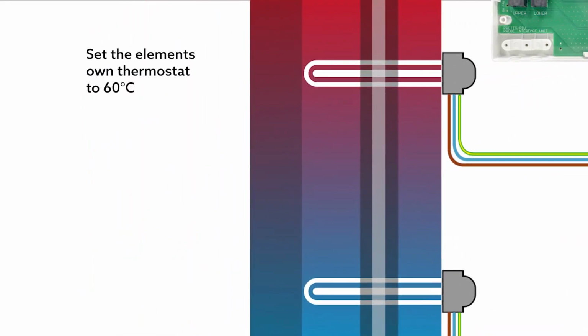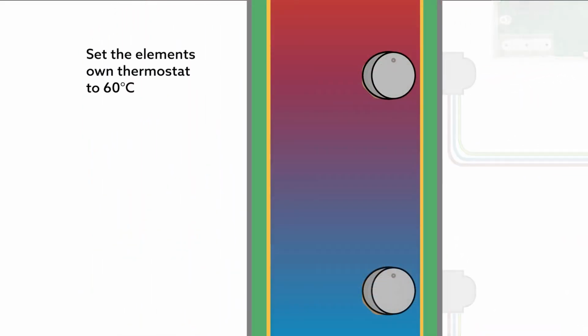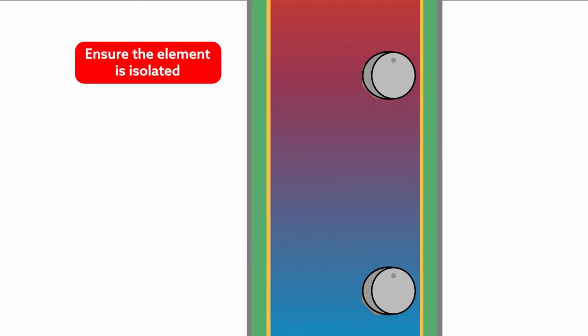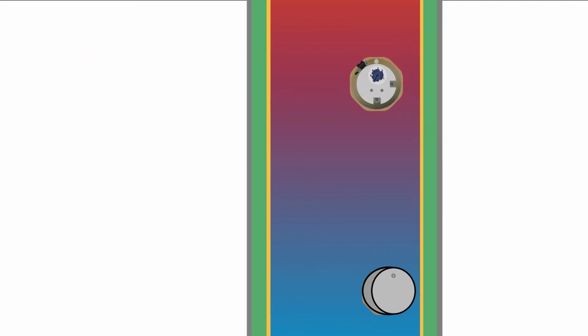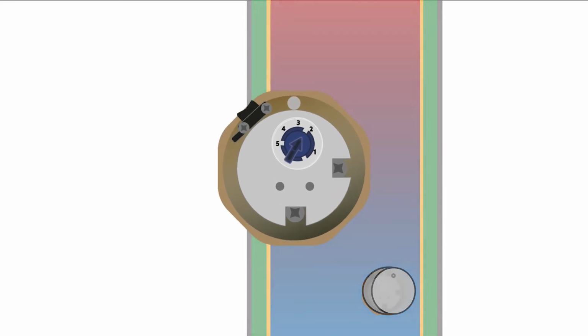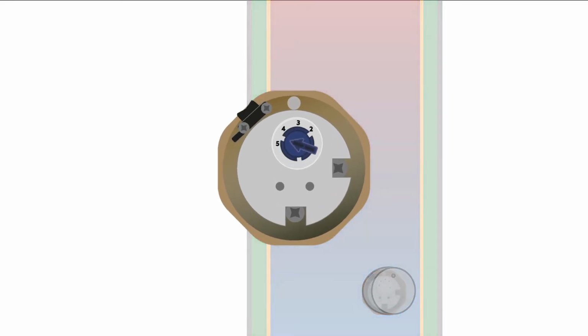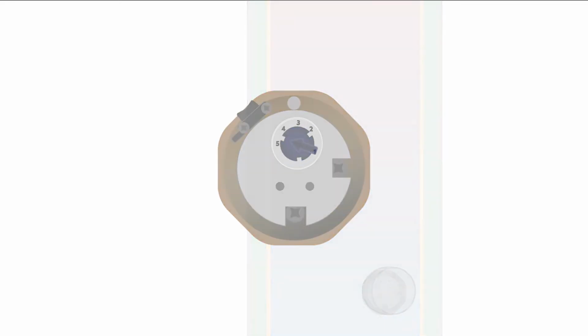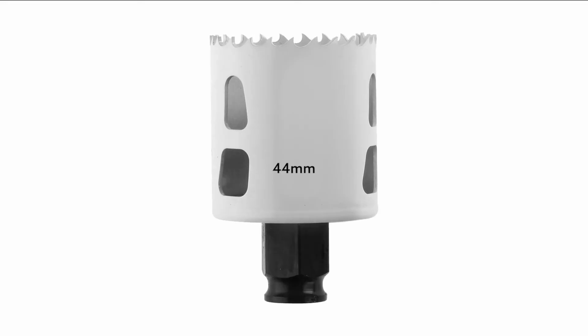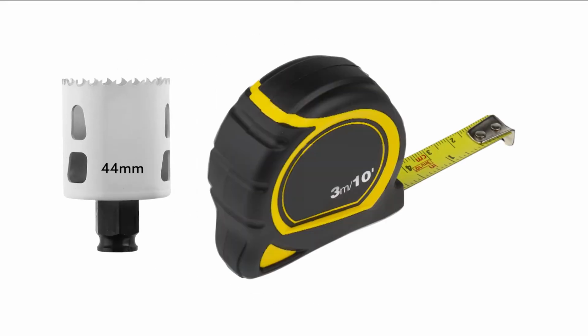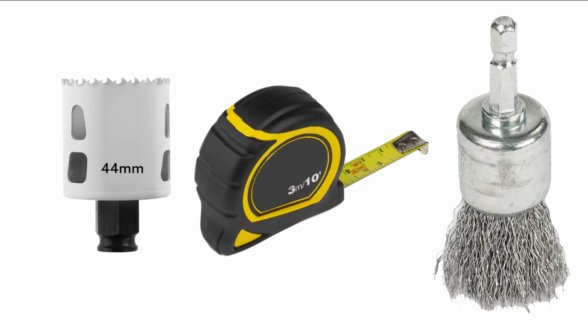On the tank, set the element's own temperature thermostat to 60 degrees C. This is so that it doesn't interfere with the Irus control regime. To achieve this, ensure the element is isolated, then remove the cap which exposes the internal thermostat and adjust the dial to the manufacturer's setting for 60 degrees C. Preparing the tank. The tank needs to be prepared to accept the probes. This requires a 44mm hole saw, tape measure, and a wire pencil brush.